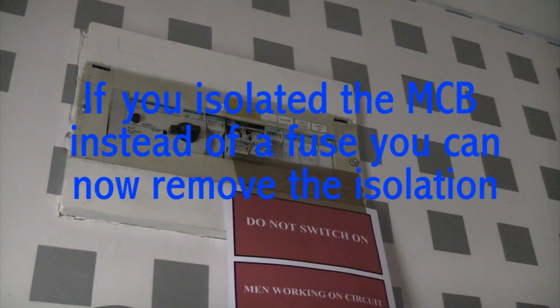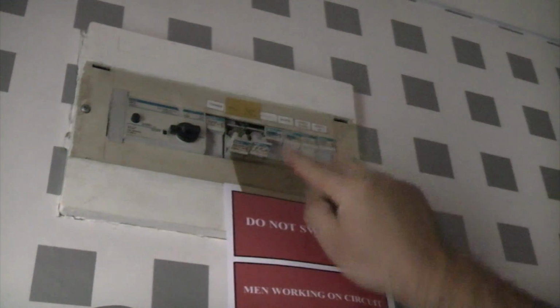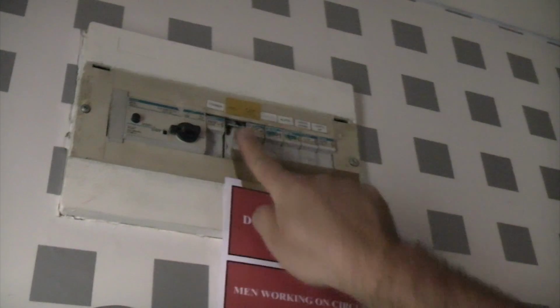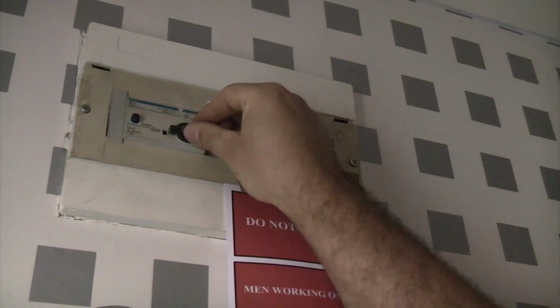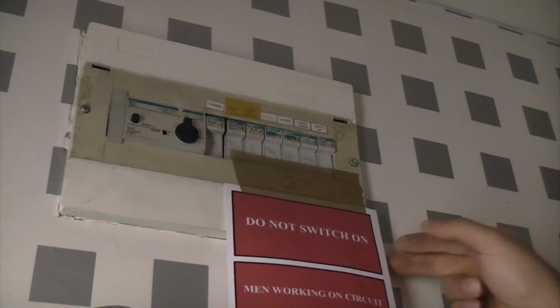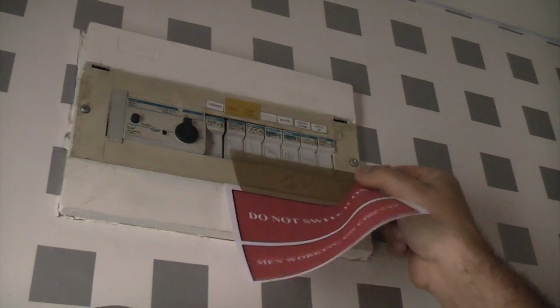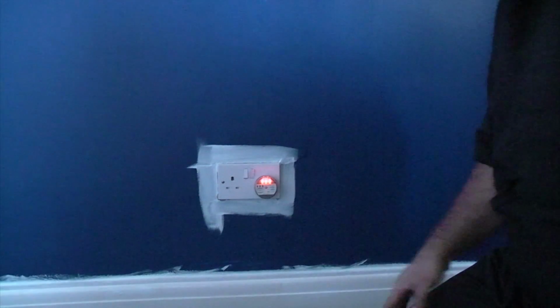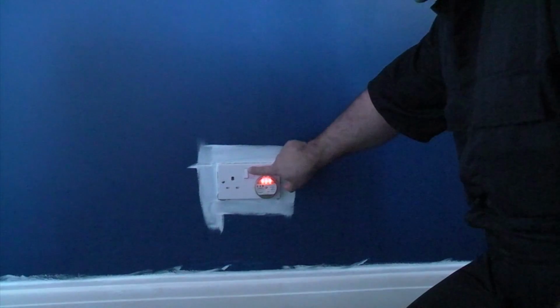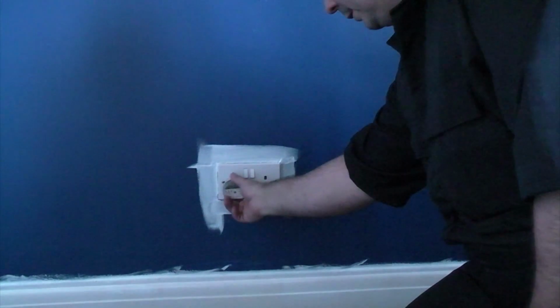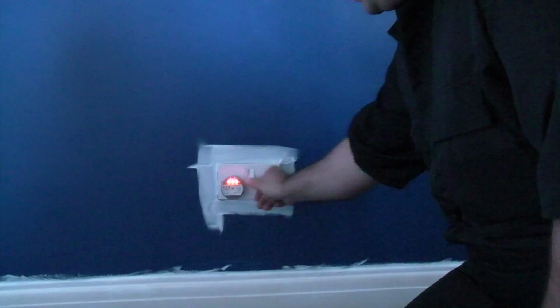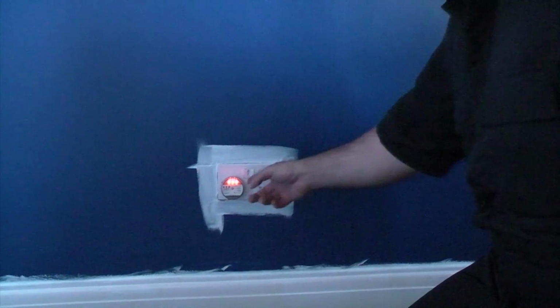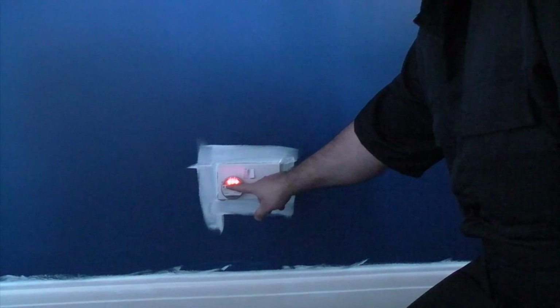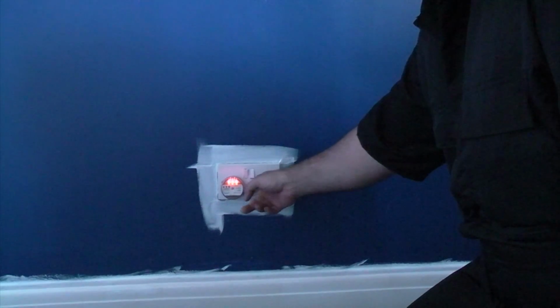So now we can replace the two fuses, just by pushing those back in. And then we can turn the main switch back on. And then we can remove the do not switch on sign. Now we can test the socket using the socket tester. You can see it's working on that side, and also on that side. And this particular kind of socket tester tells you if you've got the live, neutral and earth the correct way around.